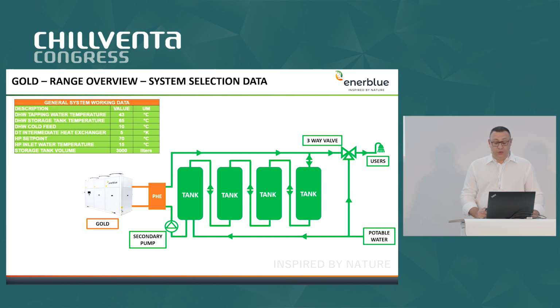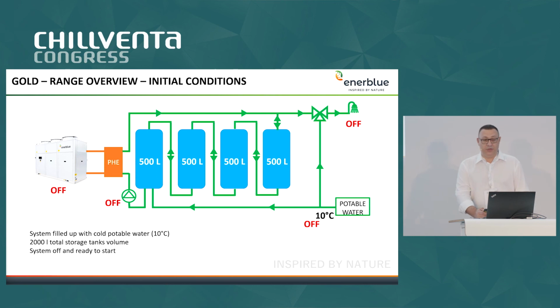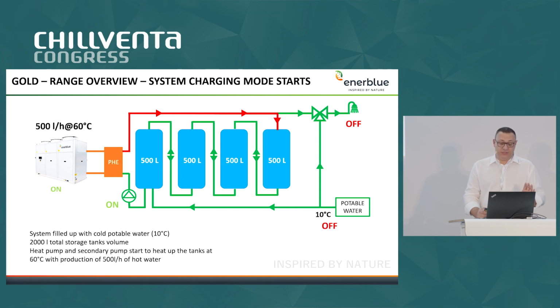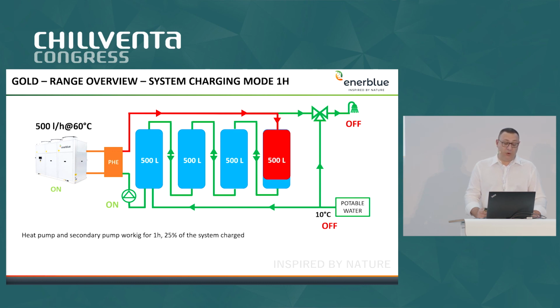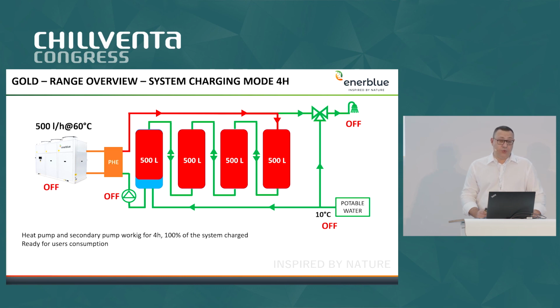Only to show you how the unit works, we start with the system with only cold water inside the tanks. In this case, there are no requests, and we are at the initial condition. Then the unit starts to charge the system. So the unit treats cold water from the tanks and produces hot water to fill up the tanks with very hot water. Our idea is to have more or less one tank filled up for each hour. So after the first hour, we will be in this condition. After 2 hours, we will have this condition. After 3, this one. And after 4 hours, we have the system full with hot water, ready to satisfy the peak.